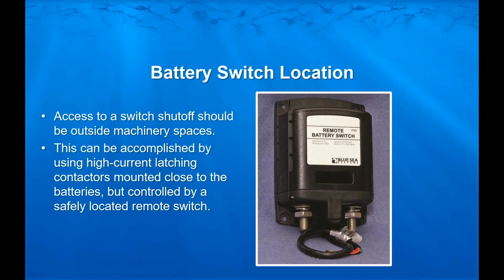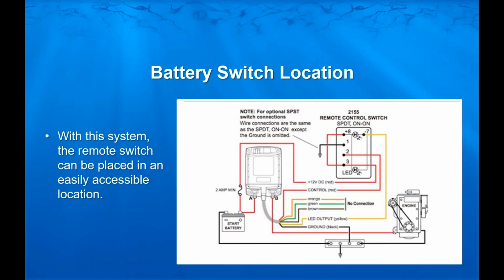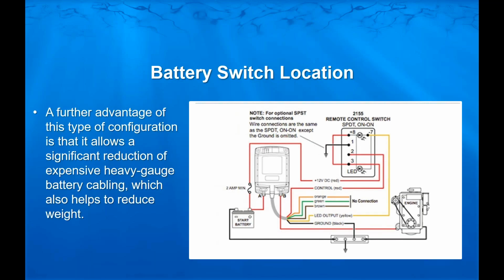You can accomplish that by using basically a solenoid switch, a high current latching contactor that's mounted close to the battery but has a remote switch safely located outside that space. With that system, the remote switch can be placed in an easily accessible location while the actual switch is close to the battery where we like to see it. Further advantage of that type of configuration is that it allows a significant reduction of expensive heavy gauge cable. Also helps to reduce weight. You're not running big cables from the battery to a battery switch that's somewhere remote and back to the source. It's certainly a much cleaner way to go, and it gets you that battery switch in a place where you can shut it off without having to gain access to a machinery space where there's a good chance the problem might be.